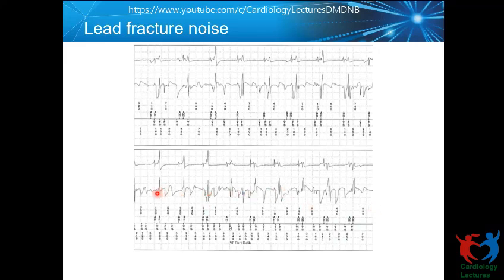So when you find a more than 30% sudden change in the impedance when the patient has been coming regularly for follow-up, and this time you found a 30% increase in the impedance, then we want to suspect a lead fracture, at least one of those strands. Then make the patient move the arm and the shoulder significantly to try to elicit the make-break signal. And if it generates this kind of noise, then it definitely is a fracture, and you may want to plan the change.